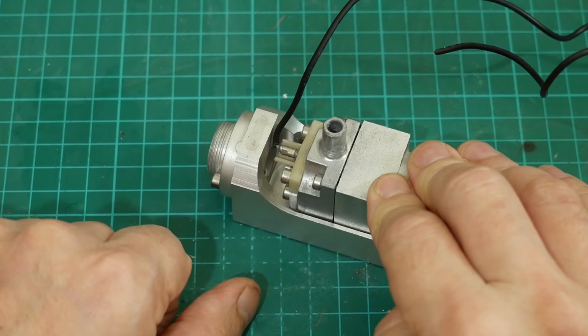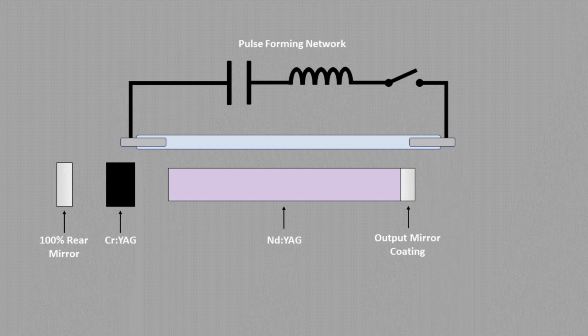Here's a diagram that shows the basic setup of the YAG laser cavity. We have a neodymium YAG rod with a partial mirror coating on one end, which serves as the output coupler. As I've said previously, I think the manufacturers of tattoo lasers do this to simplify the design and alignment. On the left, we have a high reflecting mirror which forms the other end of the cavity, and between it and the rod, we have a chromium YAG passive Q-switch.